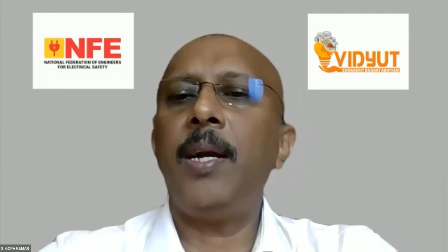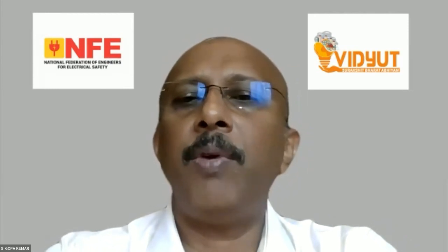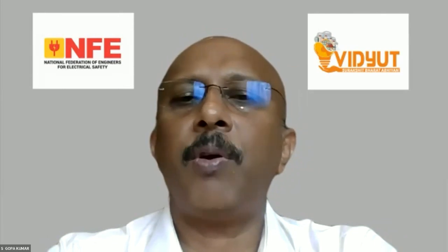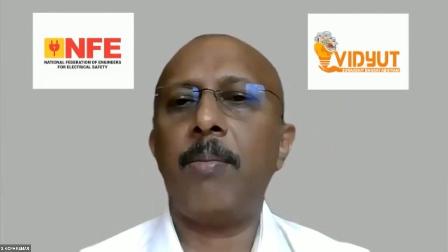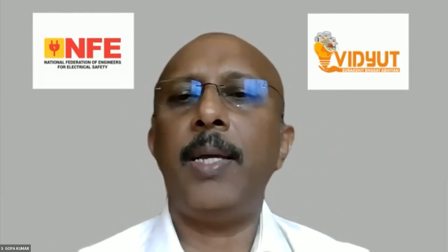Yeah. Thank you. So, a question from Mr. Ali Akbar: do you recommend the French standard LPS for a hospital or the conventional NFPA standard LPS for a hospital? Mr. Ali Akbar, please note that NFPA is not Indian. NFPA is for American people. NFPA, National Fire Protection Association, does not recommend any non-standard products. They also recommend as per the Indian standard IEC 62305 or the National Electrical Code.